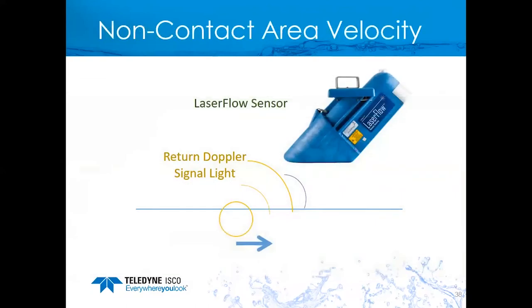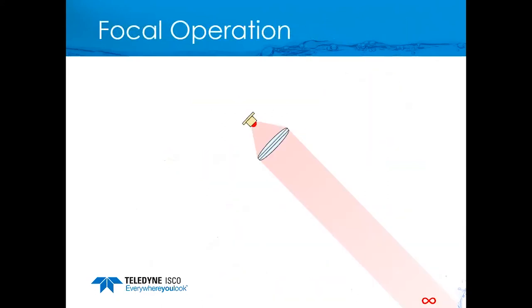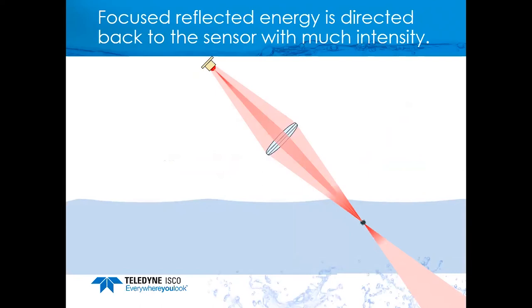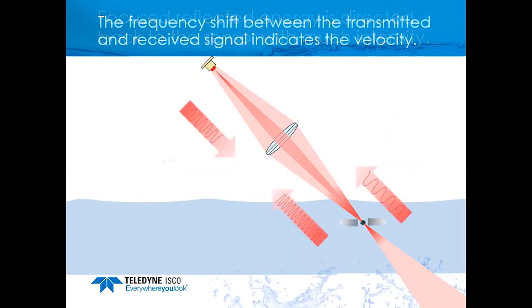A non-contact way to perform area velocity flow monitoring in an open channel is with the laser flow sensor. It uses an ultrasonic sensor to read water depth — the distance to the surface — then transmits a laser below the surface to look for peak velocity. The laser diode moves backward or forward to focus the laser through a lens below the water surface. The frequency shift from particles reflects back through the lens into the laser, determining both velocity and direction of flow.